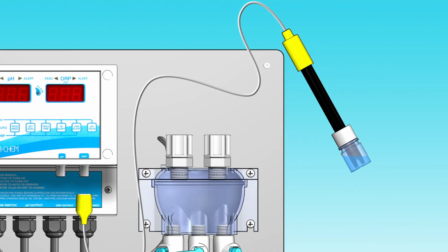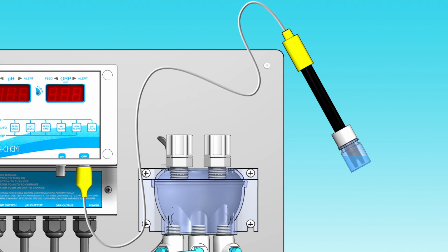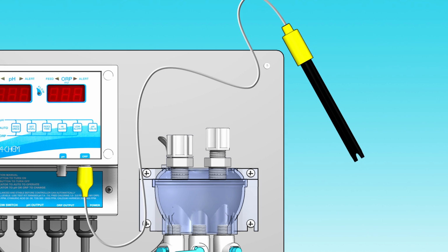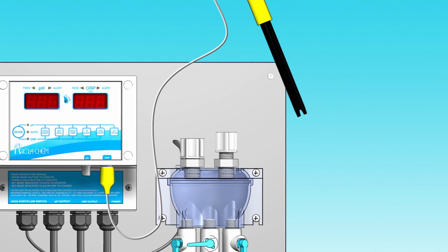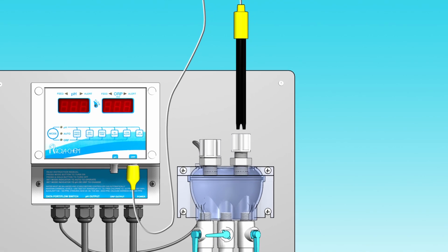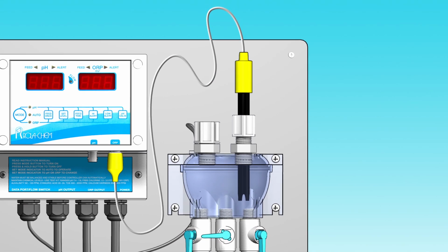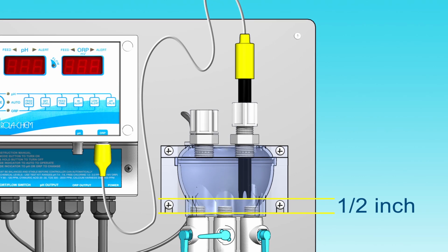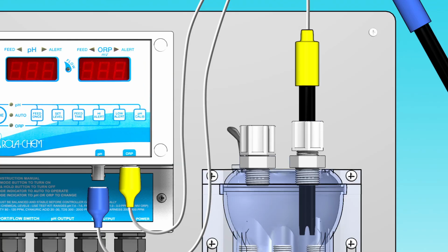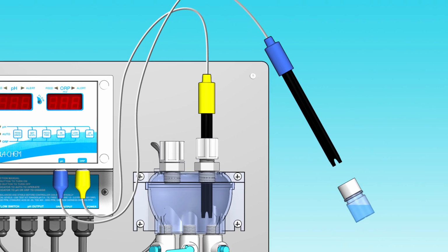To install the probes, starting with the ORP probe, plug the cable into the BNC connector on the controller labeled ORP. Remove the protective bottle from the end of the probe, seal it, and set it aside for future storage. Loosen one of the compression fittings on the top of the flow cell. Carefully insert the probe to about 1/2 inch from the bottom of the flow cell interior. Hand tighten the connector. Repeat the previous steps to connect the pH probe.